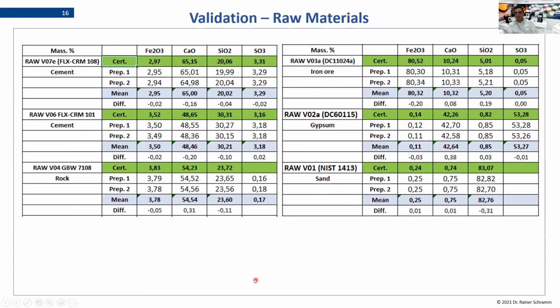Last but not least, here is a summary for you, and you know that this will be uploaded on the YouTube channel, so you can also watch this later in detail. This is a comparison for different materials like cement, a rock sample, iron ore, gypsum, and sand, also fused at different temperatures, but all measured in the same calibration. The maximum deviation we see from the certified values is 0.4%. All the rest is in a lower range and absolutely in the range which is typical for very high precision analysis.